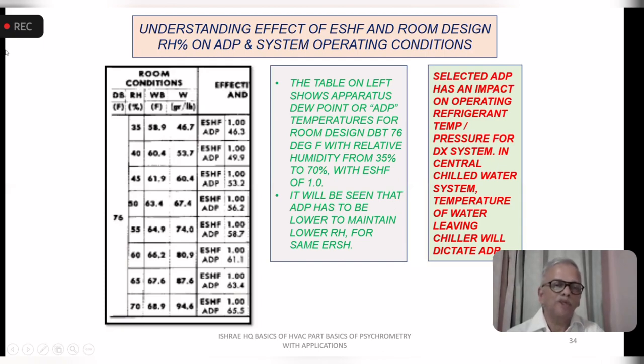Now, in simple terms, when your design humidity is, say, 40%, what you are looking for is a lower moisture level in the room. That will be a particular point on the psychrometric chart. So unless you supply air which has a moisture content lower than that of the room air, you will have a problem. Otherwise, if you supply air having higher moisture content, you will never be able to achieve the desired room condition. That's why you have to check the selected or indicated ADP, and your refrigeration system has to be selected depending on that. You have to select those operating temperatures.